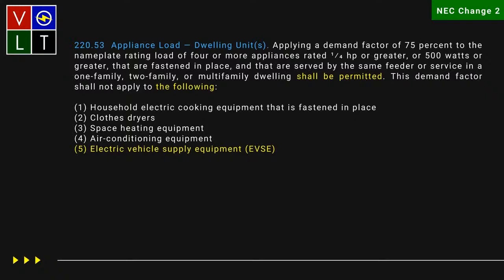Remember when I was going over this, talking about 220.53 and a full calculation, I said you'll do your general lighting and receptacle load, then your cooking equipment loads, your dryer loads, and your non-coincident loads. Everything else left went into fixed appliance. And we were asked this question.